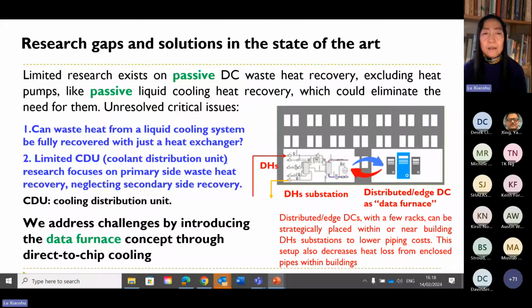To solve these problems, we introduced a new concept called data furnace through direct-to-chip cooling. The concept is illustrated in the graph on the right-hand side, which involves placing a distributed or edge data center with a few racks as a data furnace within or near building district heating substations. Here you can see that a few racks can directly heat the buildings as a data furnace. This way, piping cost and heat loss can be minimized within the building. I want to emphasize that one of the aims of our invention is to simplify piping engineering work at very low cost.